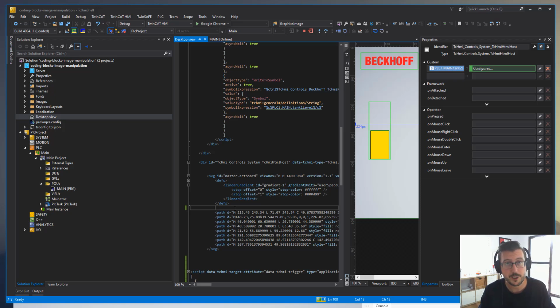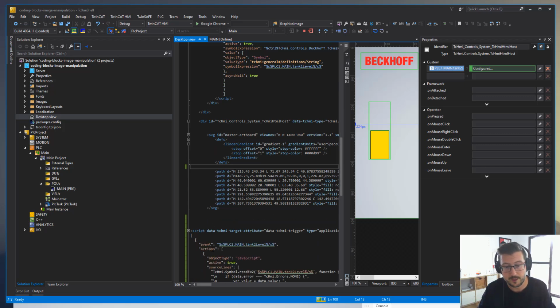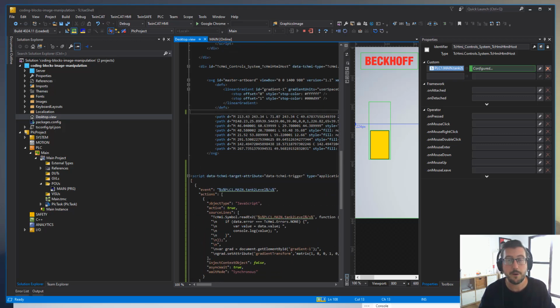It wasn't a true HTML document, and therefore TwinCAT HMI itself wasn't able to parse it correctly, and therefore any of the events that occurred after this, and it actually lists the events out just down here, by that point the parsing had already failed because it said that it didn't understand what the markup document was above. So this was actually causing this to be hidden. Every time I made one, it disappeared.